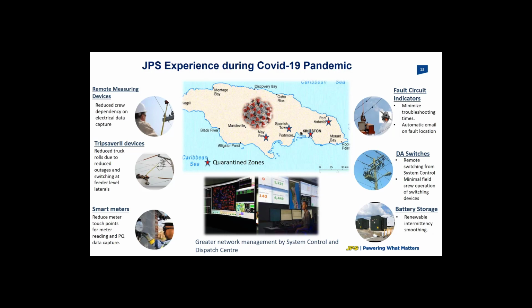For meter reading, we were able to extract meter readings from our smart meters. For other operational activities, we were able to maximize the benefits of these installations, similar to other operations island-wide. For example, our remote measuring devices reduced crew dependency on electrical data for operational planning. With trip saver technology, approximately 60% of our outages occur at the lateral level, so trip savers allowed us to drastically minimize sustained outages on these line sections, reducing truck rolls due to fewer outages, which served us well during this period.